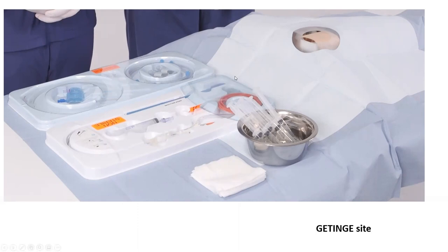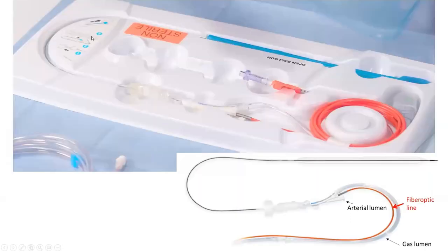The balloon pump comes with two trays. This is the first tray, which has the balloon pump catheter that I explained earlier with the three lumen: arterial lumen, helium gas lumen, and fiber optic line. And it's very easy to prep. The balloon itself is covered with that blue plastic, and you should leave it on until you're ready to advance the balloon pump, just so that you don't unfurl the balloon. So we leave it on.